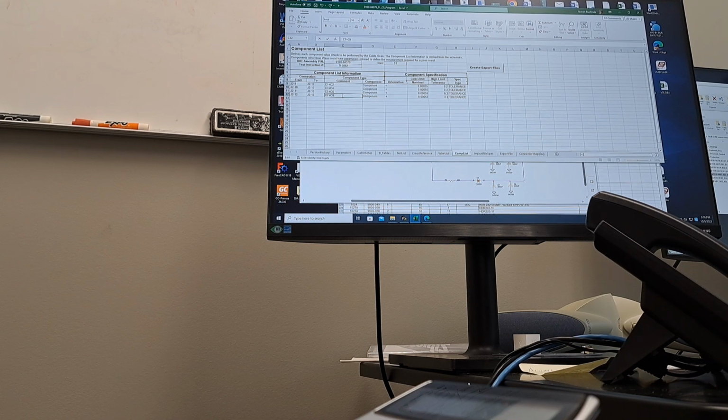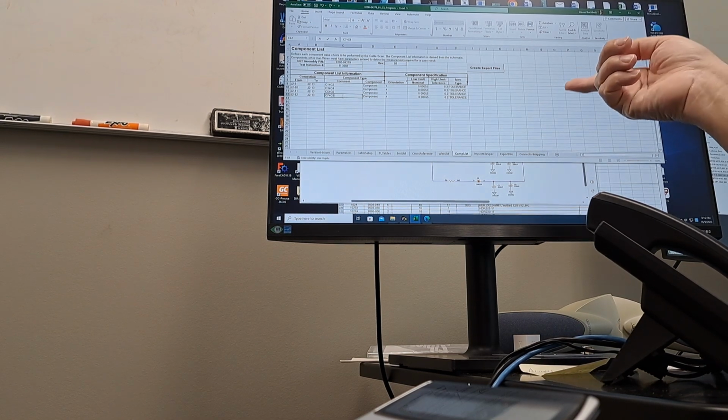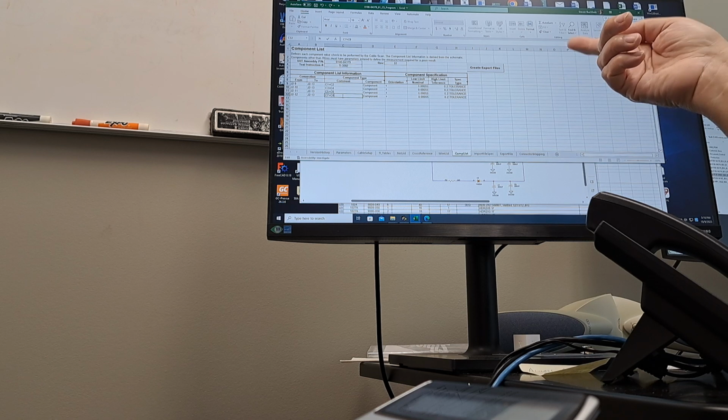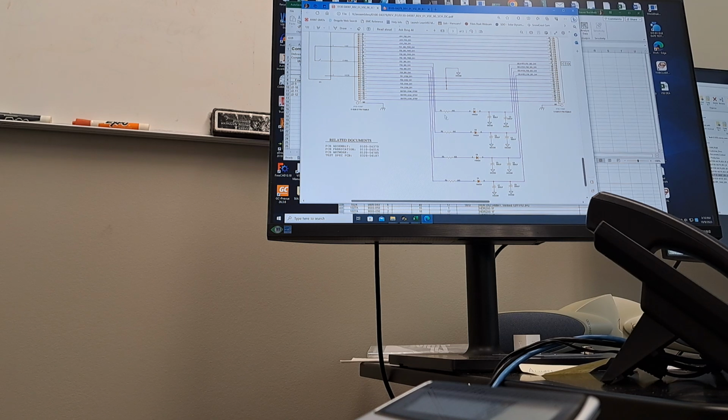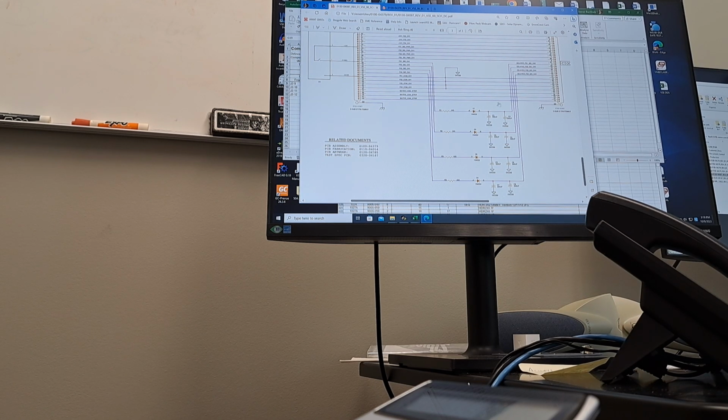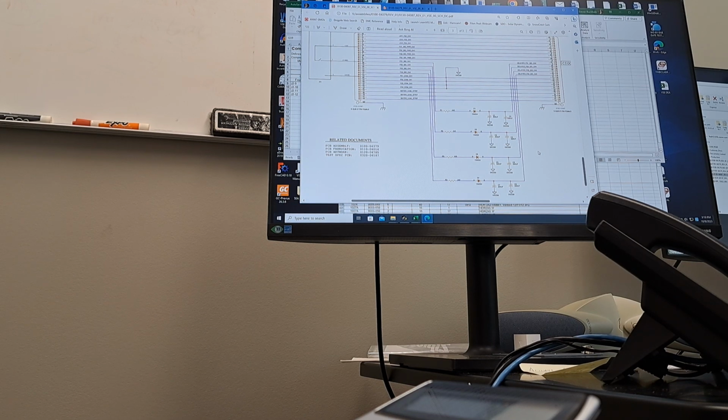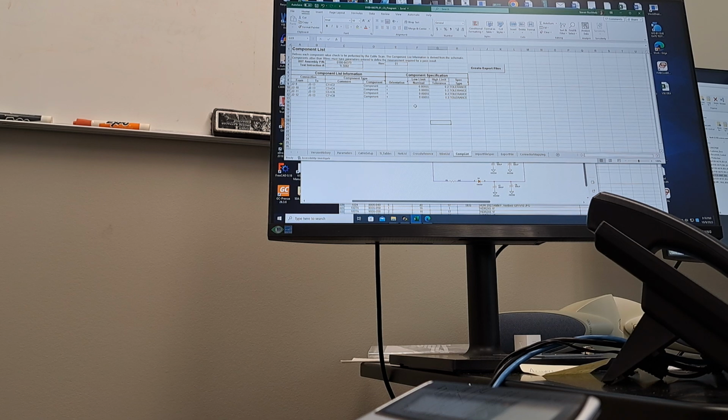And then, you know, the main thing that you're putting this in here for is that if there's a failure, the person that's running the cable scan has some information that they can use for troubleshooting. Okay, so now we're going to say we can't test these guys. We've got all of this other stuff already done. So we're just going to add these four capacitors in effect, and we're going to call it good. Okay, so we got that. That's all expressed in here.